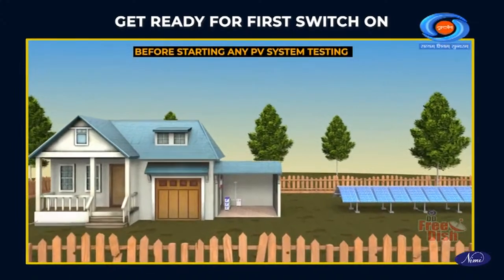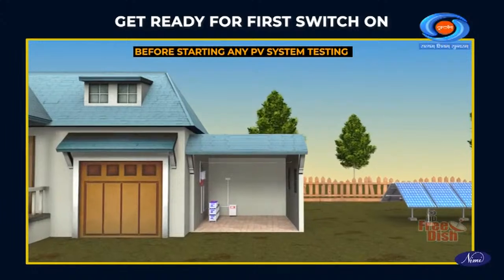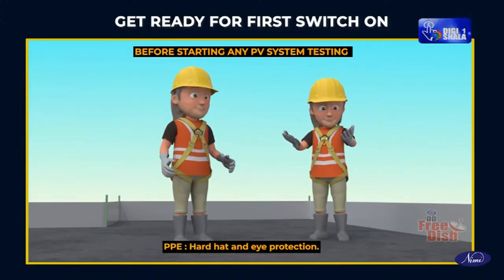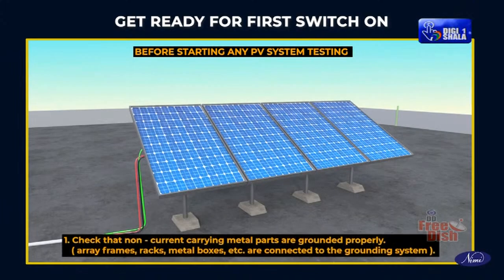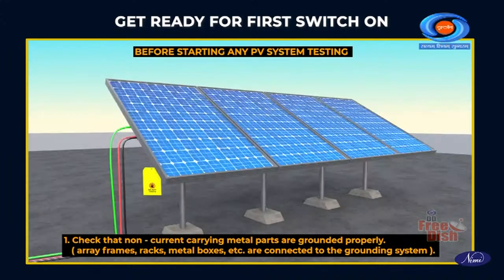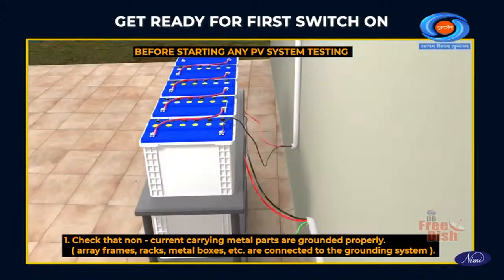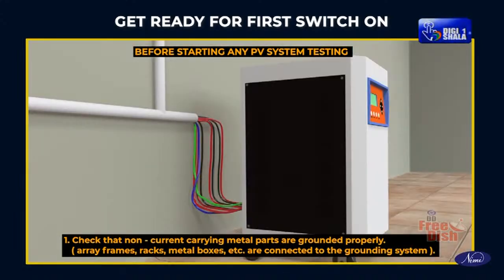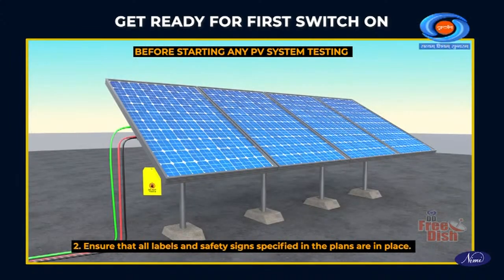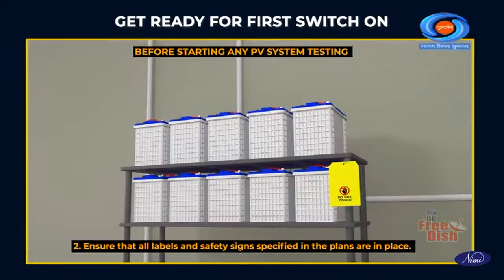Before starting any photovoltaic system testing, PPE: hard hat and eye protection. Check the non-current carrying metal parts are grounded properly, which are array frames, racks, metal boxes, etc. are connected to the grounding system. Ensure that all labels and safety signs specified in the plans are in place.